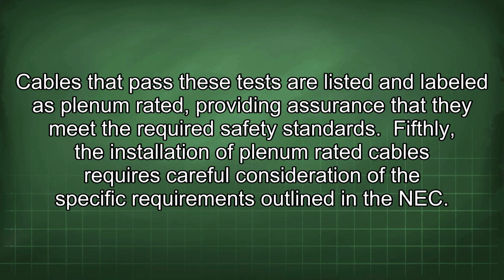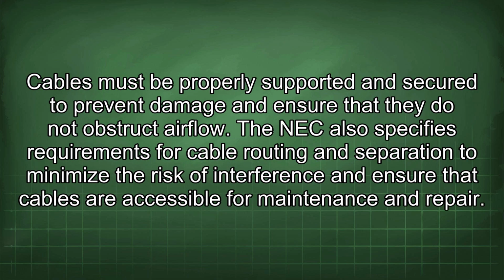Fifthly, the installation of plenum-rated cables requires careful consideration of the specific requirements outlined in the NEC. Cables must be properly supported and secured to prevent damage and ensure that they do not obstruct airflow. The NEC also specifies requirements for cable routing and separation to minimize the risk of interference and ensure that cables are accessible for maintenance and repair.